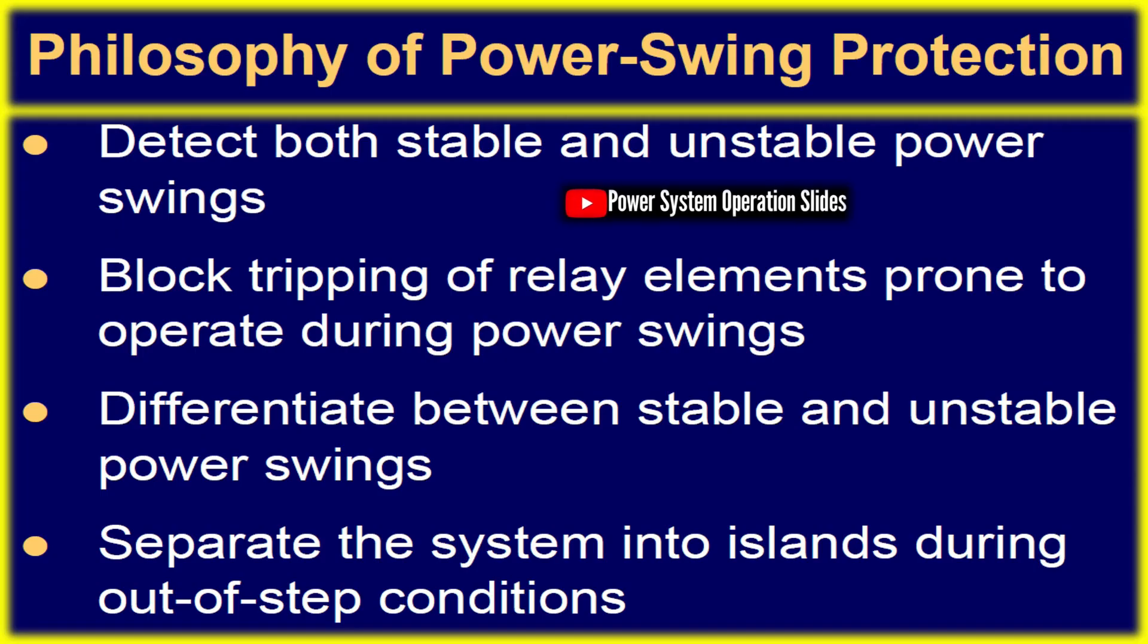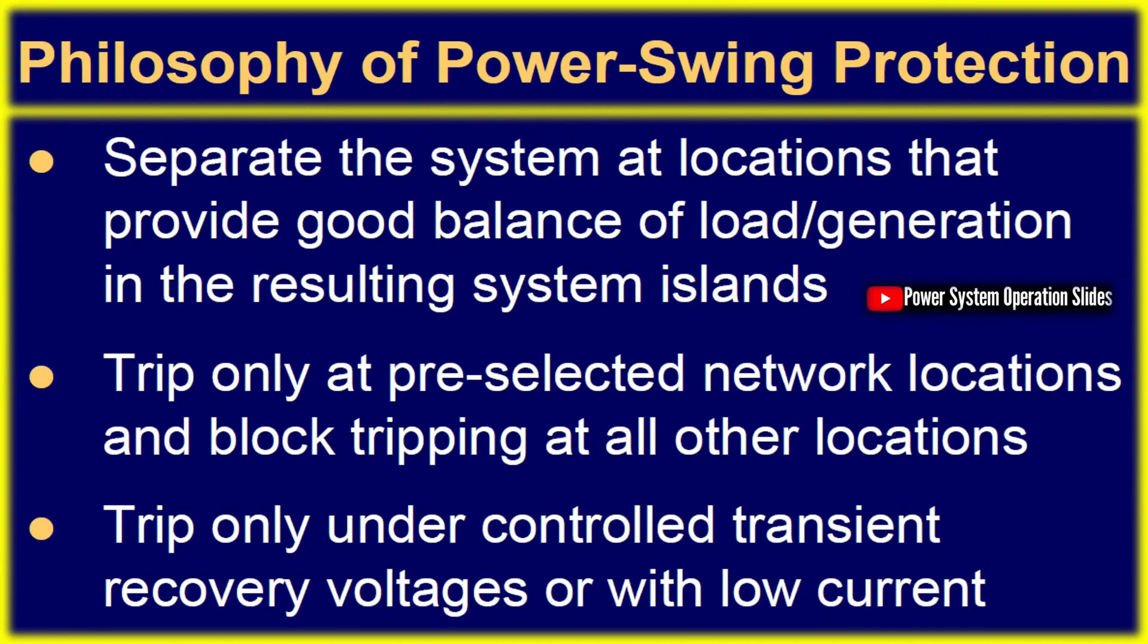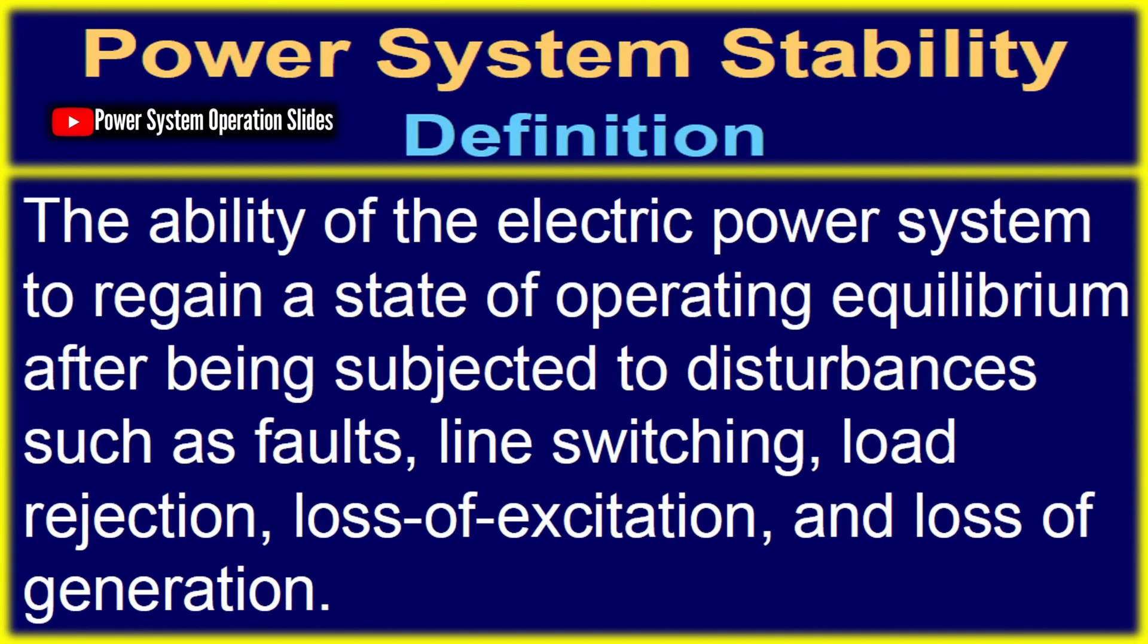Since designing a system to fully prevent such rare simultaneous failures is extremely costly, utilities employ special protection systems and remedial action schemes, such as under-frequency and under-voltage load shedding, along with controlled tripping of loads or generation, to minimize disturbance impacts.